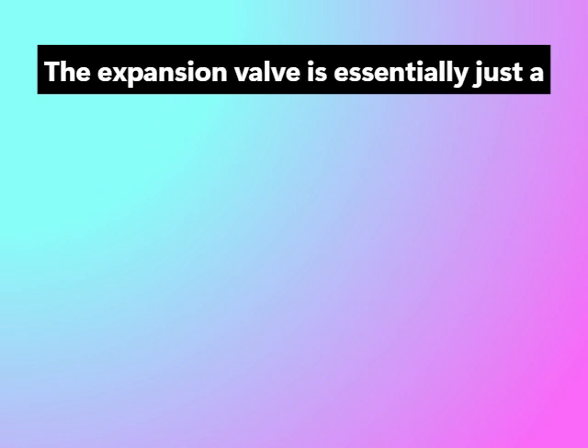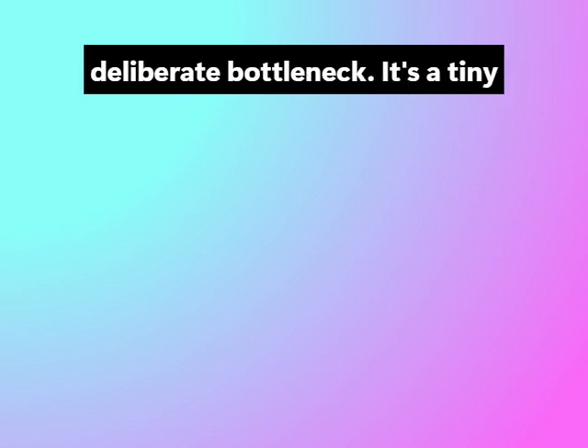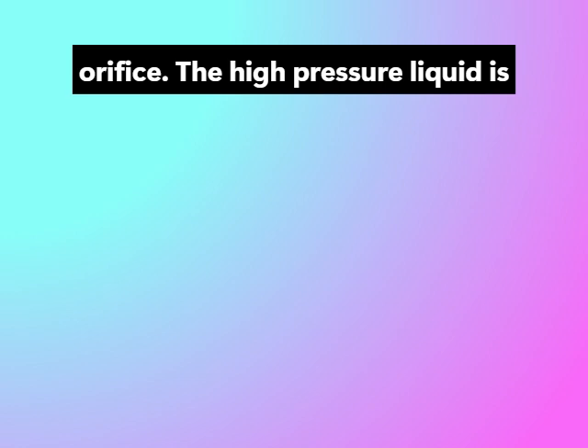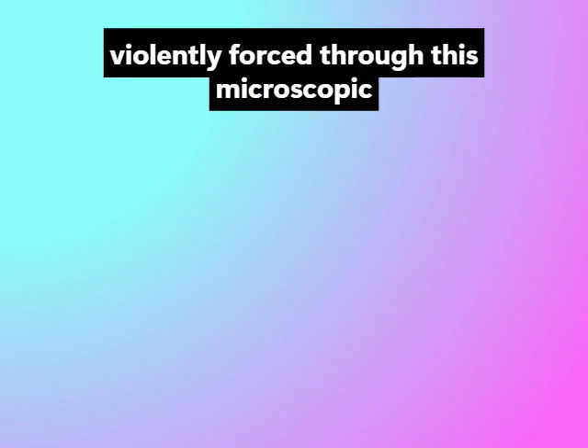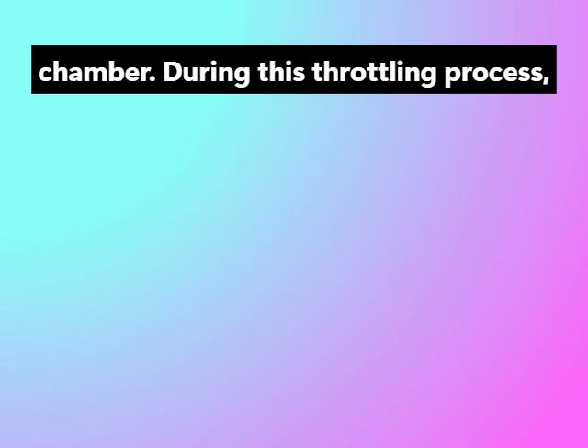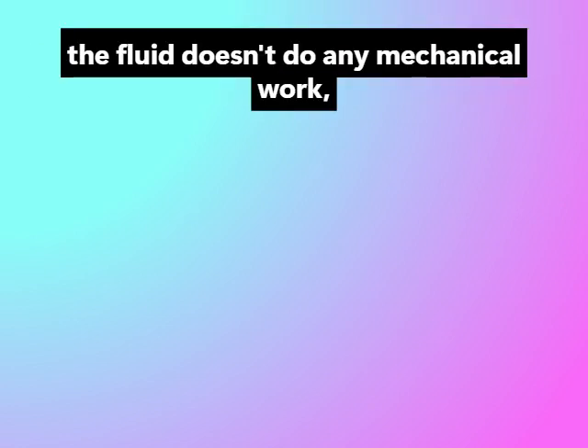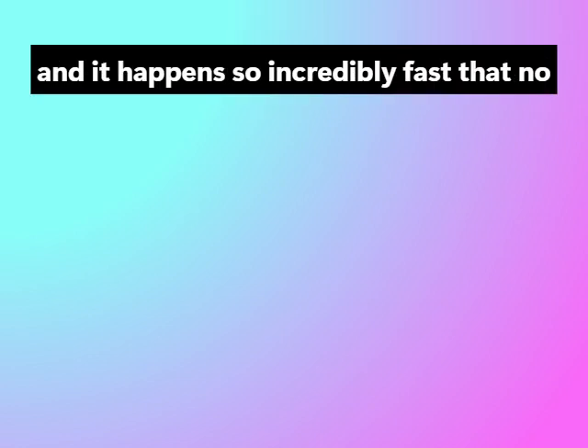The expansion valve is essentially a deliberate bottleneck, a tiny orifice. The high-pressure liquid is violently forced through this microscopic opening into a much larger, lower-pressure chamber. During this throttling process, the fluid doesn't do any mechanical work, and it happens so incredibly fast that no heat is exchanged with the outside environment.